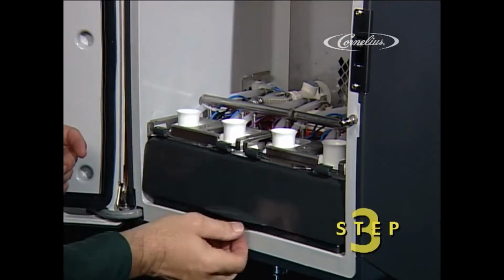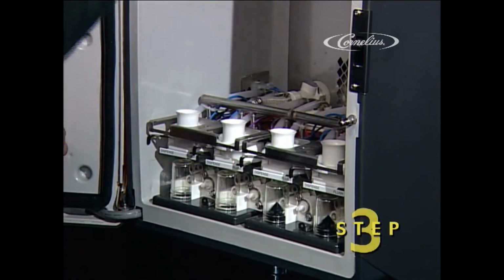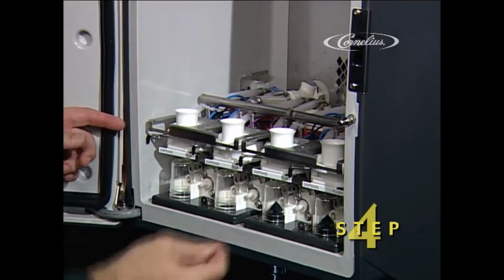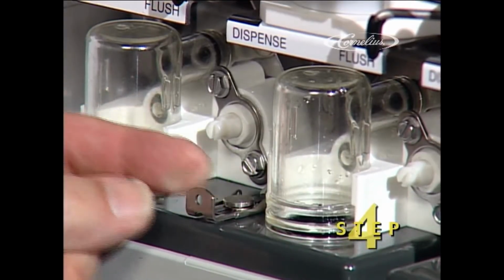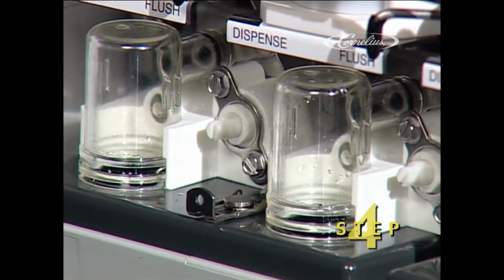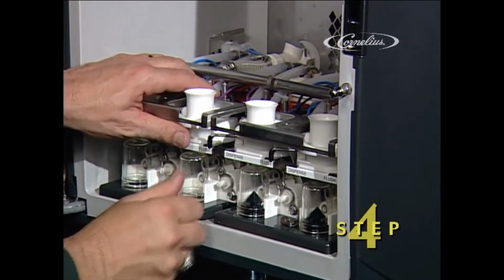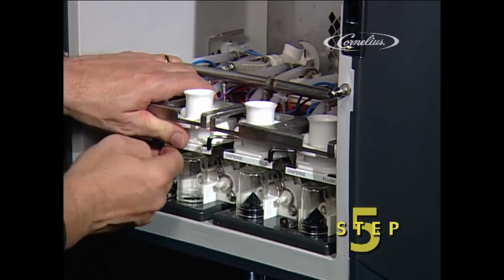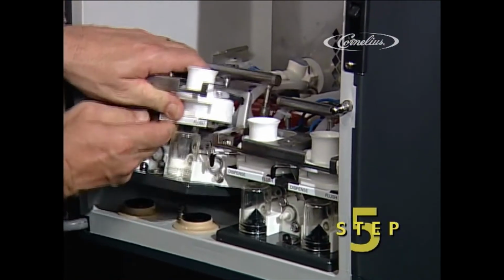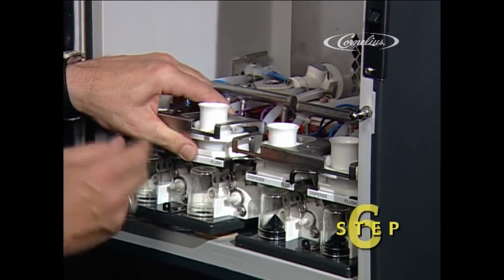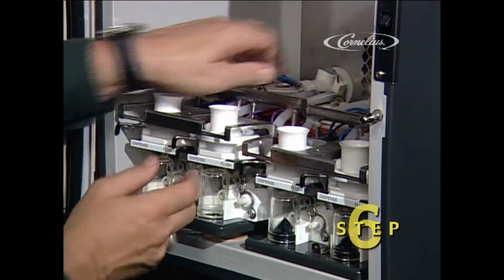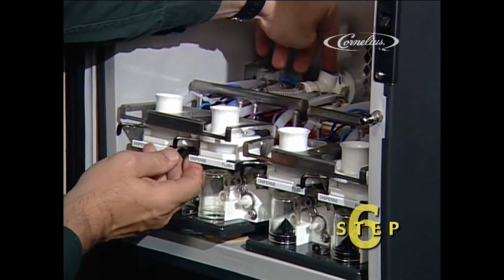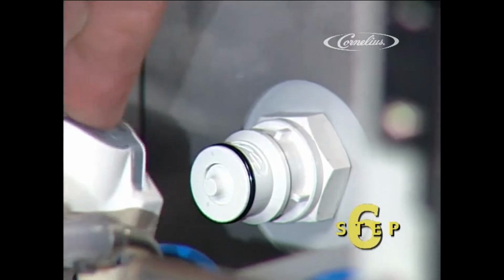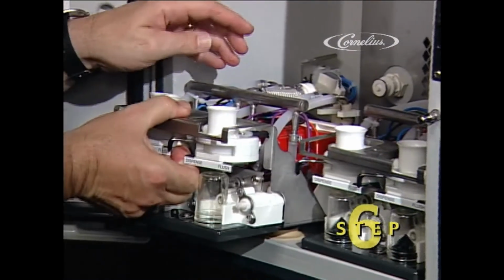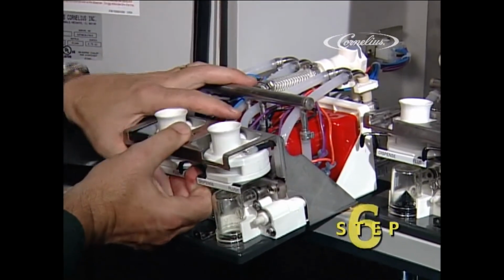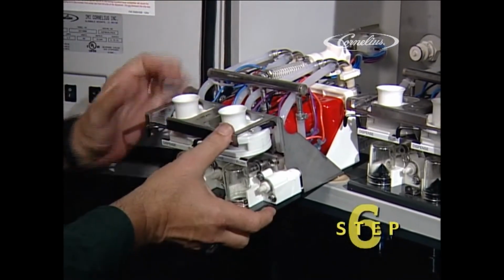Step 3. Pull and lift the front flap door out. Step 4. Unlock the platform clips. Pull on the catch and slide it back to unlock the platform clips from the dispenser. Step 5. Gently lift the platform straight up and begin to pull it forward. Step 6. Release the water connector. The water connector is released by pressing the gray button on the water coupler. After releasing the water connector, pull the tray up and finish pulling it forward until the platform connection is separated from the dispenser.